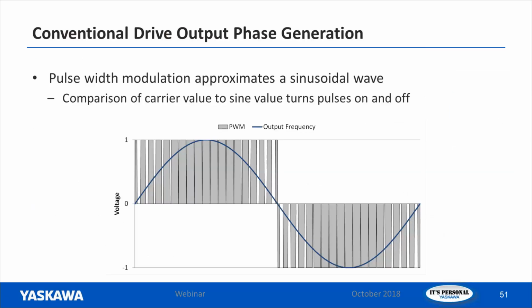Here's a depiction of the pulse width modulation. With the IGBTs, we're able to pulse the voltage here in the positive direction to make a square wave, and then here, again, in the negative direction to make a square wave. The key here is we're trying to get the motor to draw a sine wave of current. And we are able to control that. The width of a pulse is actually the time duration of a pulse. So on the edges of the square, we've got shorter pulses, which will result in a lower current draw. But here towards the middle, we'll have a longer pulse. The longest pulses are in the middle to give us a high current draw. So even though we've got a square wave of voltage, we're able to get a sine wave of current to go out to that motor.